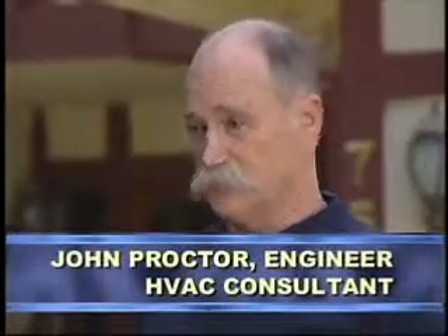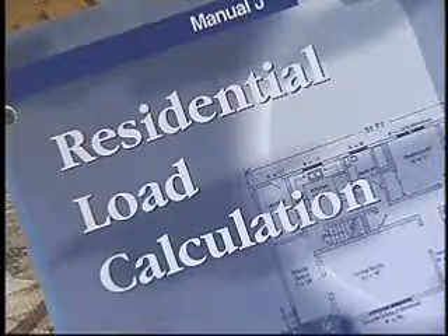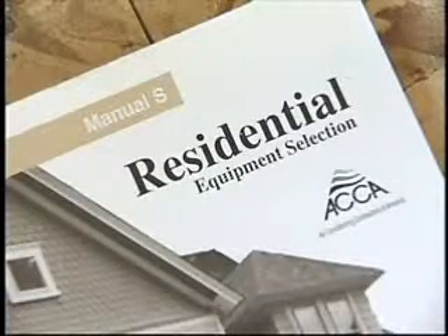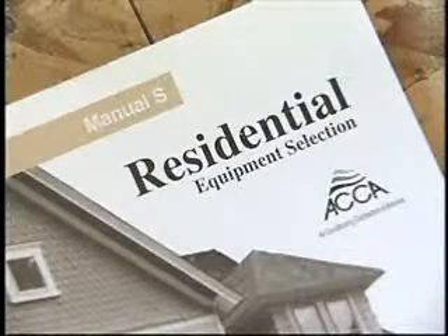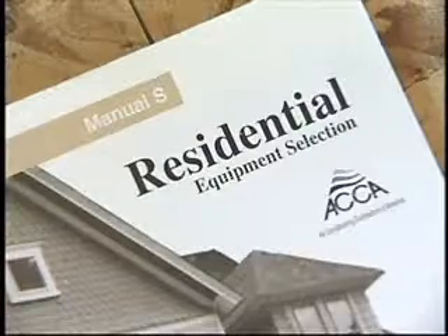Since most homes' systems are oversized by a ton or more, what are your tips for sizing systems? Well, the first thing that they should insist on is to get a load calculation. They have to know that the contractor has sat down, figured out how much window area there was, what kind of windows they are, whether or not they're shaded or not. And from that, they need to calculate what the real size air conditioner is that they need. It's a very standard method of doing that. It's ACCA Manual J, and getting the right size air conditioner is ACCA Manual S. And they should insist that for every single house that they build, the AC contractor provides that information to them.